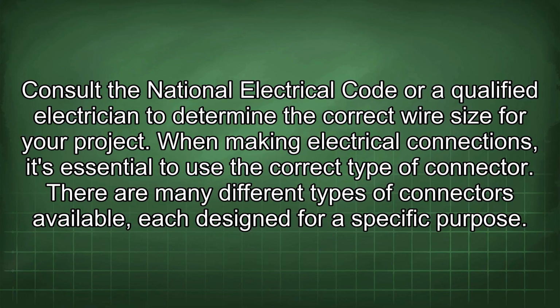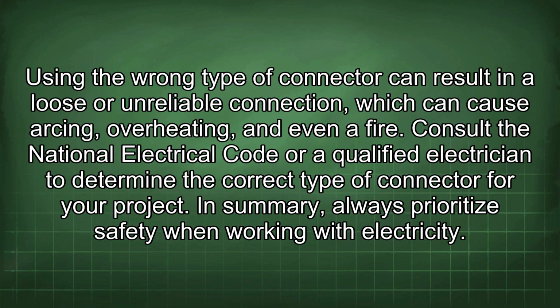When making electrical connections, it's essential to use the correct type of connector. There are many different types of connectors available, each designed for a specific purpose. Using the wrong type of connector can result in a loose or unreliable connection, which can cause arcing, overheating, and even a fire. Consult the National Electrical Code or a qualified electrician to determine the correct type of connector for your project.